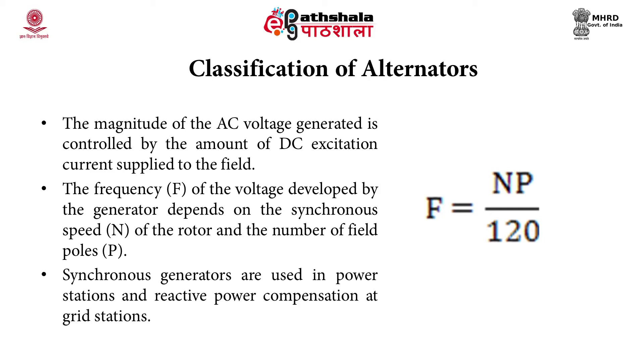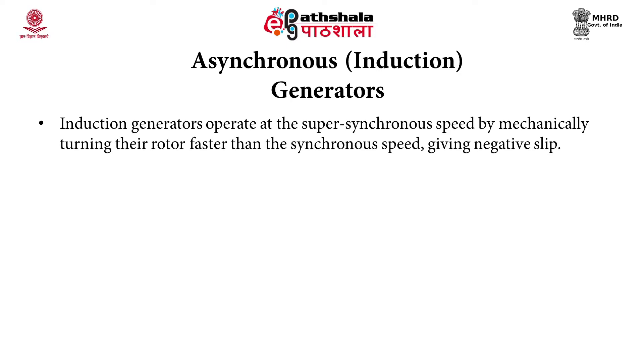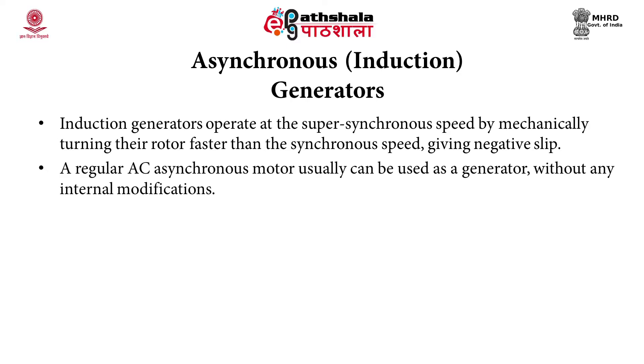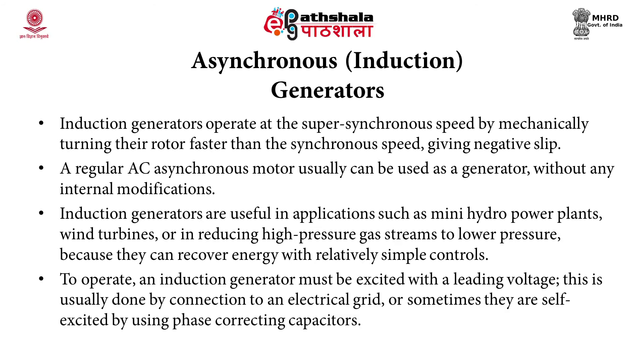Synchronous generators are used in power stations and for reactive power compensation at grid stations. Asynchronous generators are also known as induction generators. They operate at super-synchronous speed by mechanically turning their rotor faster than synchronous speed, giving negative slip. A regular AC asynchronous motor can usually be used as a generator without internal modification. Induction generators are useful in applications such as mini-hydropower plants, wind turbines, or reducing high-pressure gas streams to lower pressure. To operate, an induction generator must be excited with a leading voltage, typically by connection to an electric grid or by using phase-correcting capacitors.